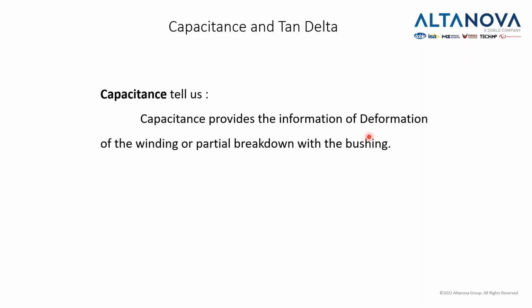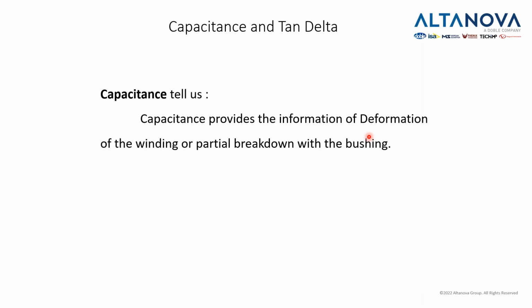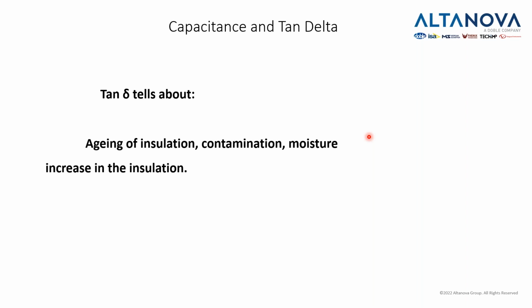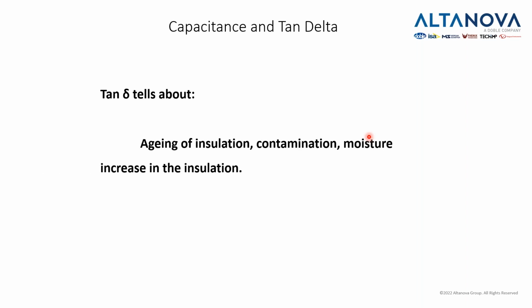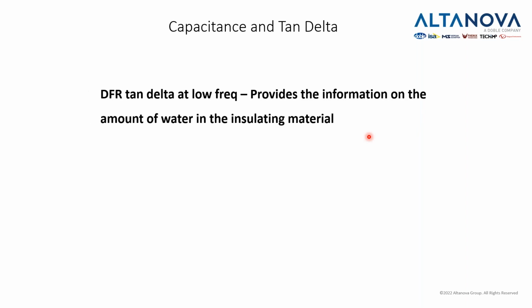Now, moving on, we still have quite a lot to cover and not too much time. So capacitance will provide the information of the deformation of the winding or a partial breakdown of the bushing, while the tan delta will tell us about aging of insulation, possible contamination, moisture increase. In general, it will show us that we have issues with the insulation.